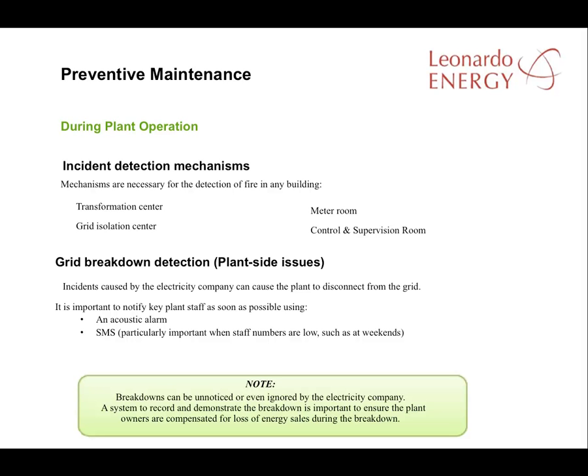For every potential incident, you will need to establish an incident detection mechanism. In your planning, you should rank every potential incident according to its probability and the damage it might produce. For example, a fire in the control or supervision room is not very probable, but the potential damage is severe — therefore a detection mechanism for that incident is a high priority. Breaks in the grid connection are often the responsibility of the electricity company that the solar plant supplies. However, these breakdowns can sometimes pass unnoticed by the electricity company or perhaps even be ignored by them. So a detection mechanism that alerts a person with responsibility for the solar plant whenever there is a disconnection from the grid is important. If the breakdown is not properly noted or recorded, it could affect the compensation that the solar plant will receive.